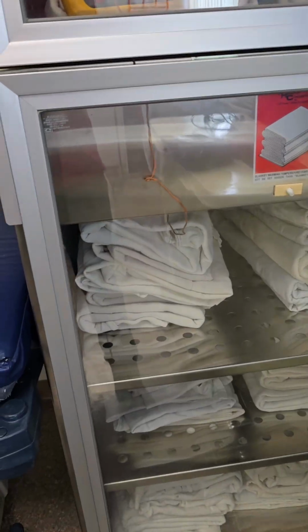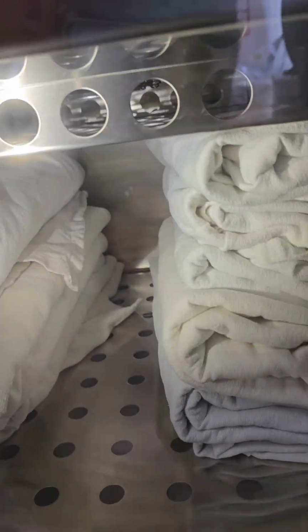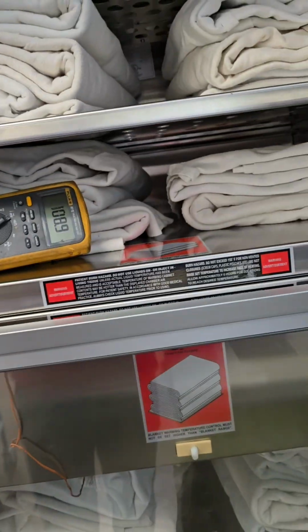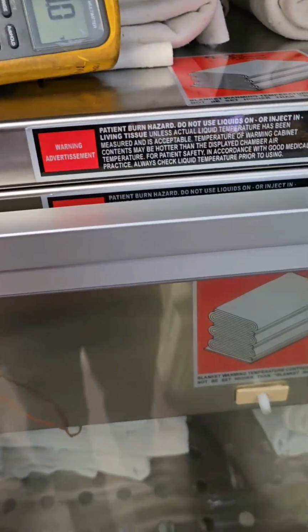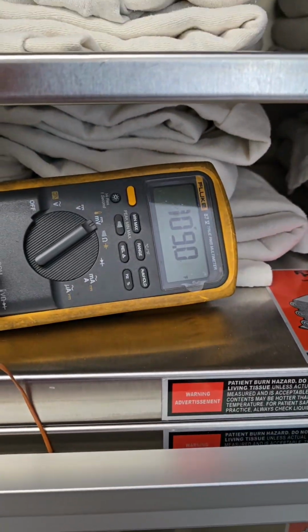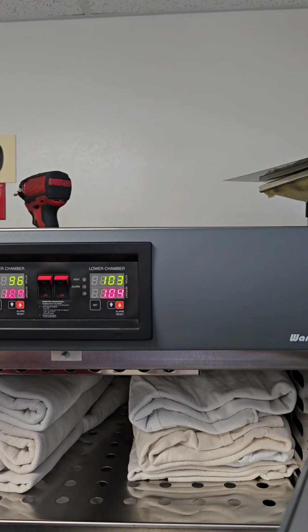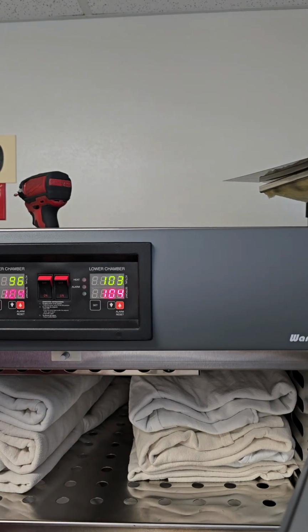Alright, once you close the door, double check. Make sure the cable didn't move your probe anywhere. I can see we're still good. Alright. I don't want to cook my thermometer, but I said give it about 10 minutes. I can see here. Let these two adjust. Okay, so like I said, been about 10 minutes. You can't see both, but my display appears as 103. Down here I'm saying about 113, so we're off by about 10.